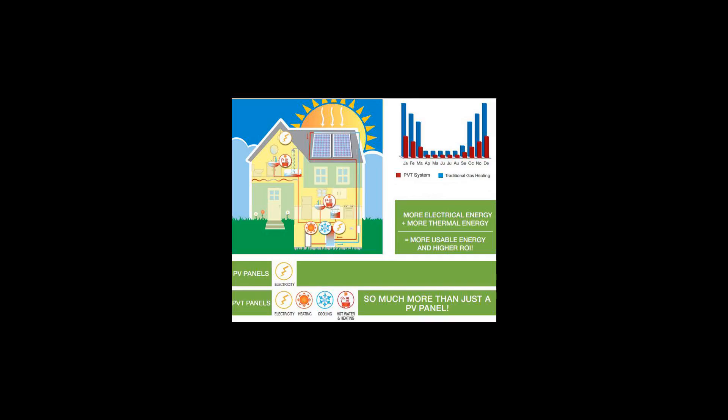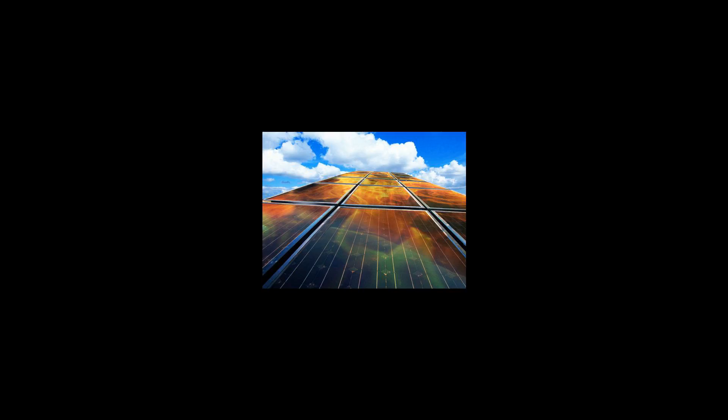Although this is an effective method, it causes the thermal component to underperform compared to a solar thermal collector. Recent research showed that photovoltaic materials with low temperature coefficients, such as amorphous silicon, allow the PVT to be operated at high temperatures, creating a more symbiotic PVT system. This advantage can be tuned by controlling the dispatch strategy of thermal annealing cycles in any region of the world.